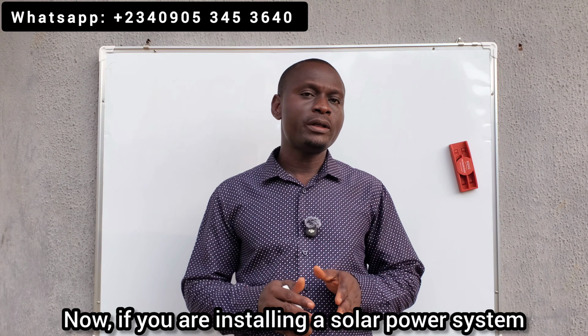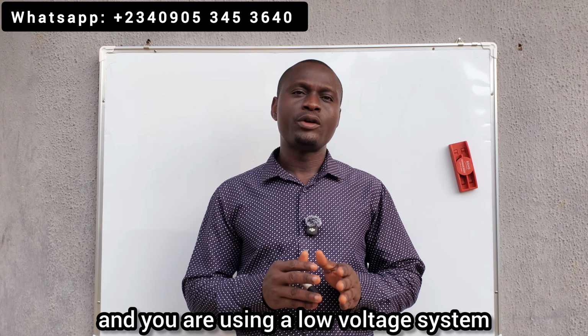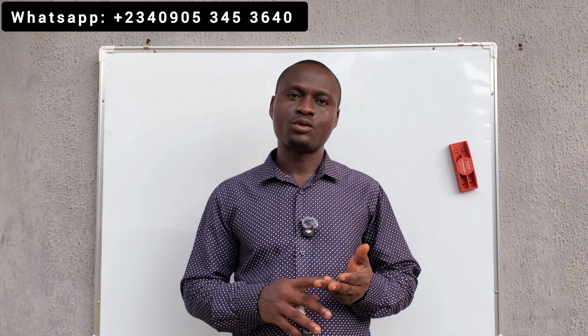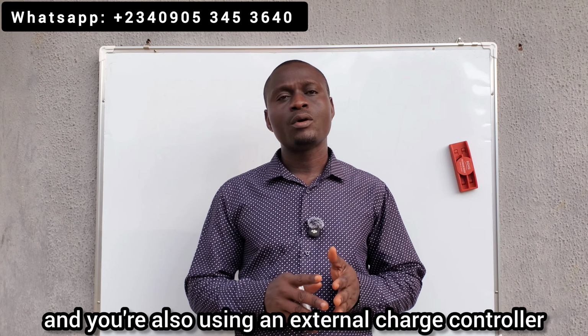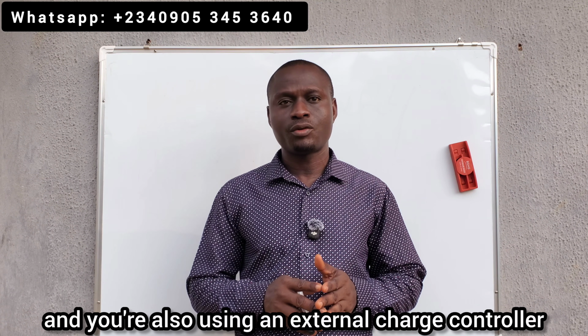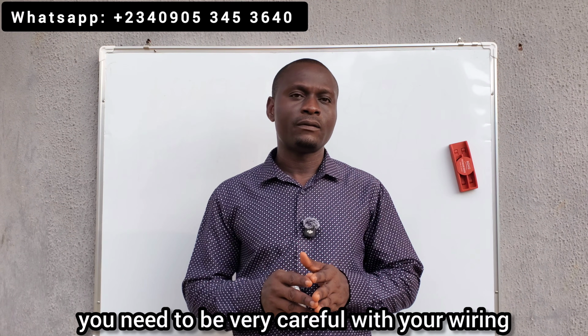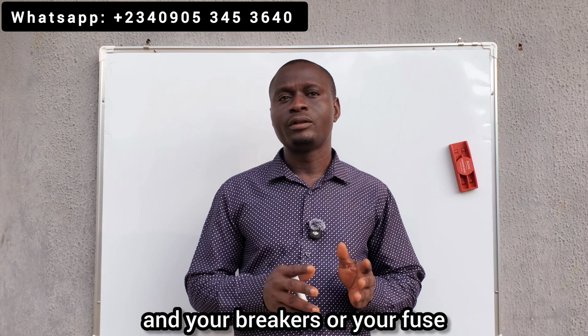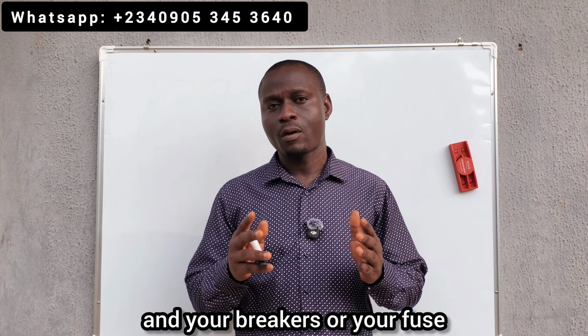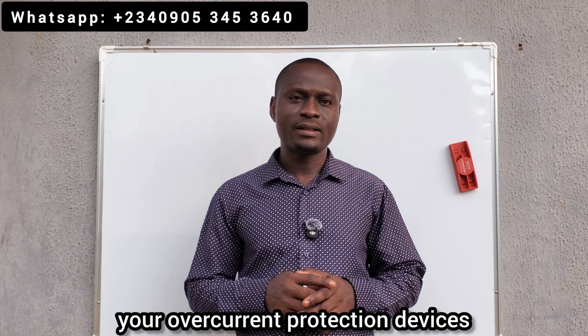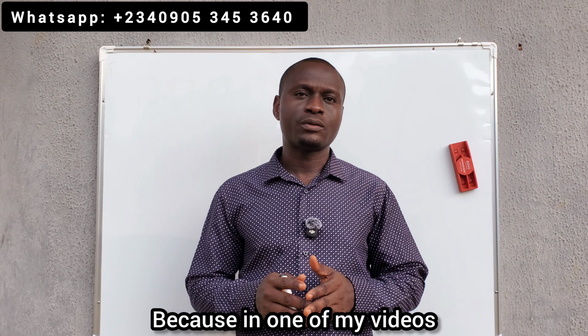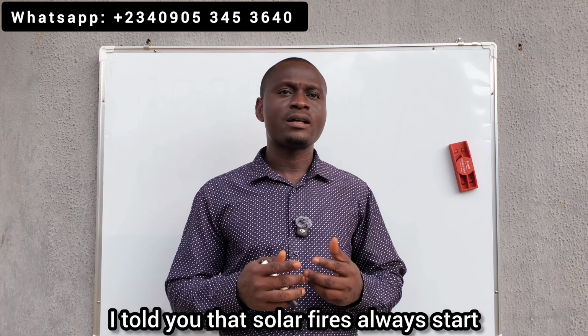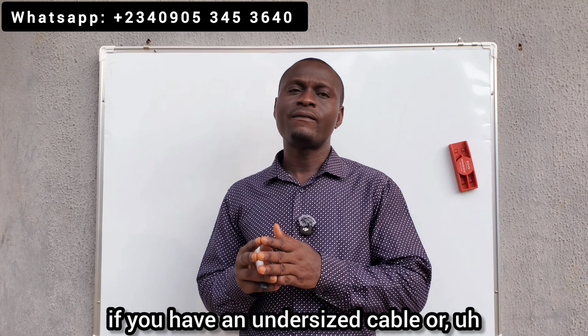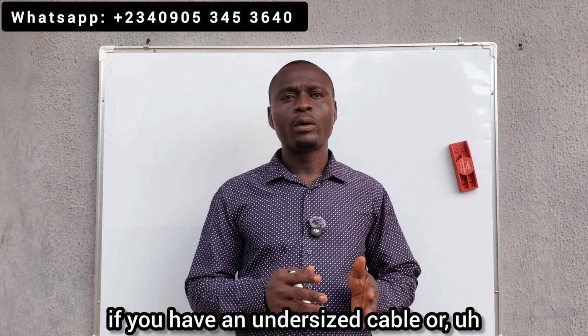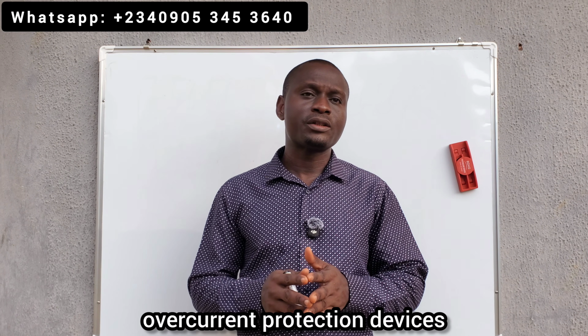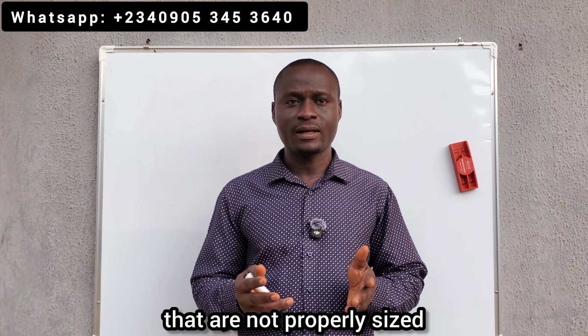If you are installing a solar power system using a low voltage system, 12 volts or 24 volts, and you're also using an external charge controller, you need to be very careful with your wiring and your breakers or fuse, your overcurrent protection devices. In one of my videos, I told you that solar fires always start if you have an undersized cable or overcurrent protection devices that are not properly sized.